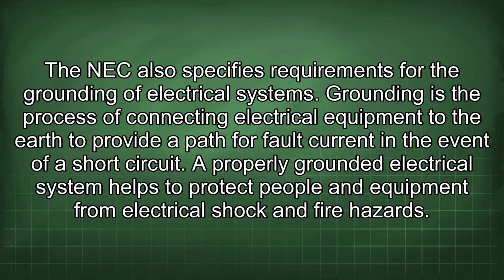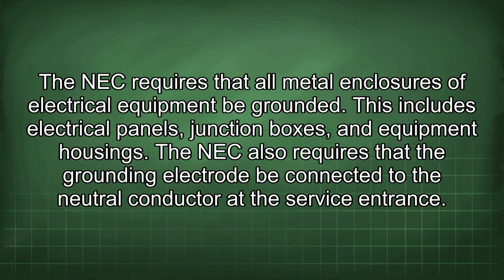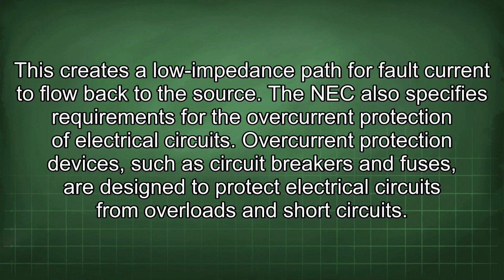The NEC also specifies requirements for the grounding of electrical systems. Grounding is the process of connecting electrical equipment to the earth to provide a path for fault current in the event of a short circuit. A properly grounded electrical system helps to protect people and equipment from electrical shock and fire hazards. The NEC requires that all metal enclosures of electrical equipment be grounded. This includes electrical panels, junction boxes, and equipment housings. The NEC also requires that the grounding electrode be connected to the neutral conductor at the service entrance. This creates a low impedance path for fault current to flow back to the source.